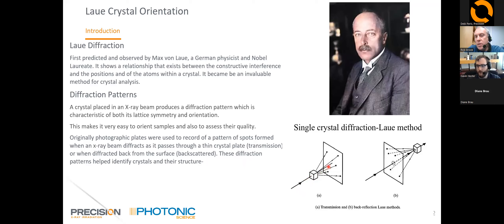In the bottom right corner you can see a diagram with the X-ray beam coming in and hitting a crystal — the X-rays diffract from the crystal and hit a plate, which is called transmission Laue. On the right is the backscattered method, which is the one we use on our systems, where the X-ray beam passes through the detector, hits the crystal, and the X-rays are diffracted back onto the detector plane.